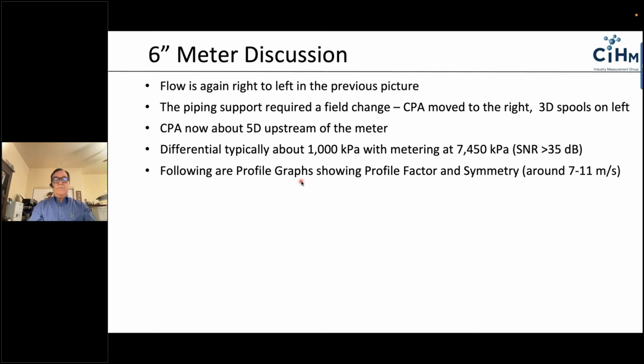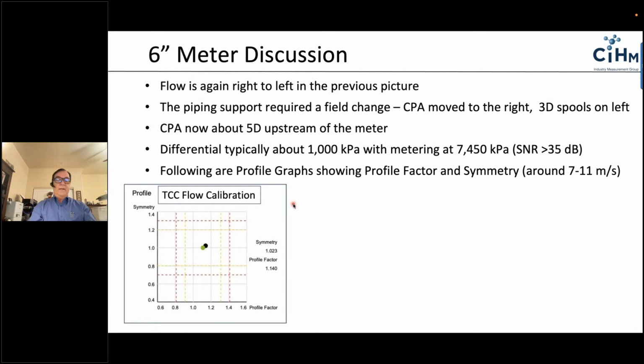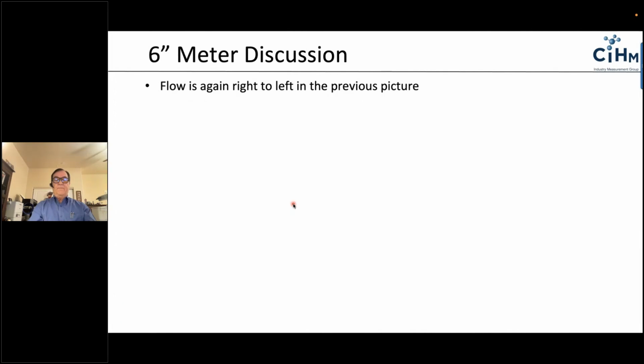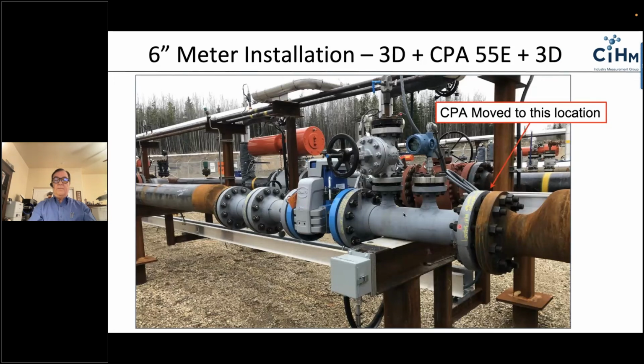So let's take a look at the flow graphs from this meter. What does the profile look like? Hey, John? Yes. We did put the 55E on this meter install as well, right? Yes. The 55E is located right here upstream of the approximately 5D spool piece. It's a little less than 5D. So it's right at the outlet of the eccentric reducer from 10 to 6, flow conditioner here, and then straight pipe into the meter.